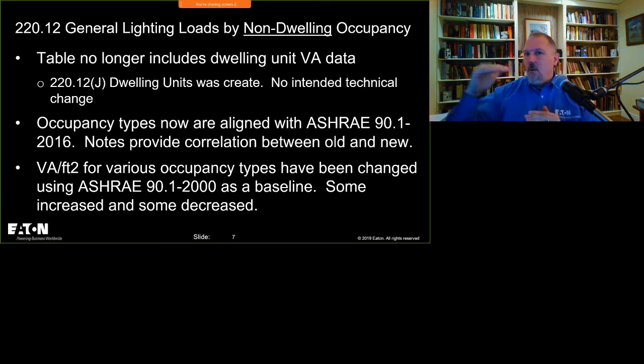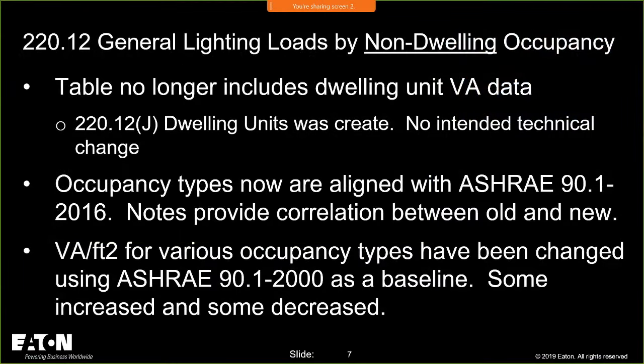So we just did not want to lower that number too low, but we wanted to recognize the fact that we are moving into a world of higher efficiency types of solutions down at the end use, down on the ends of those branch circuits. Specifically, lighting was low-hanging fruit. So in any case, we focused in on the 2016 version. And again, the VA per square foot for a lot of these installations did come down.